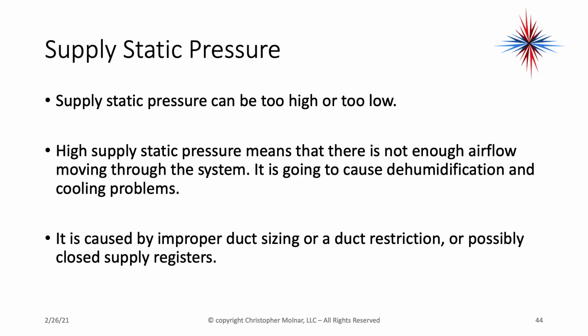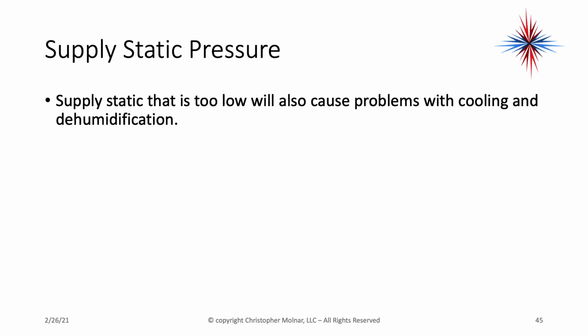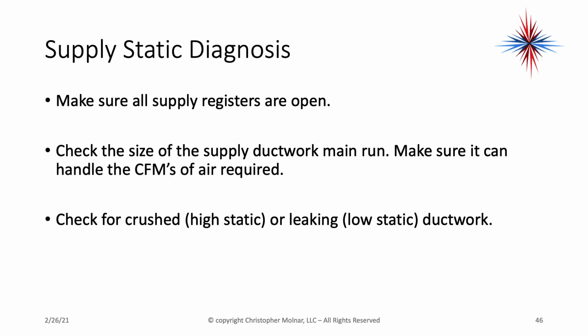Supply static pressure issues also exist. Supply static pressure can be too high or too low. High supply static means that there's not enough airflow moving through the system. It's going to cause you dehumidification and cooling problems. It is caused by improper duct sizing or duct restriction or possibly closed supply registers. If supply static pressure is too low, it's going to also cause problems with cooling and dehumidification.